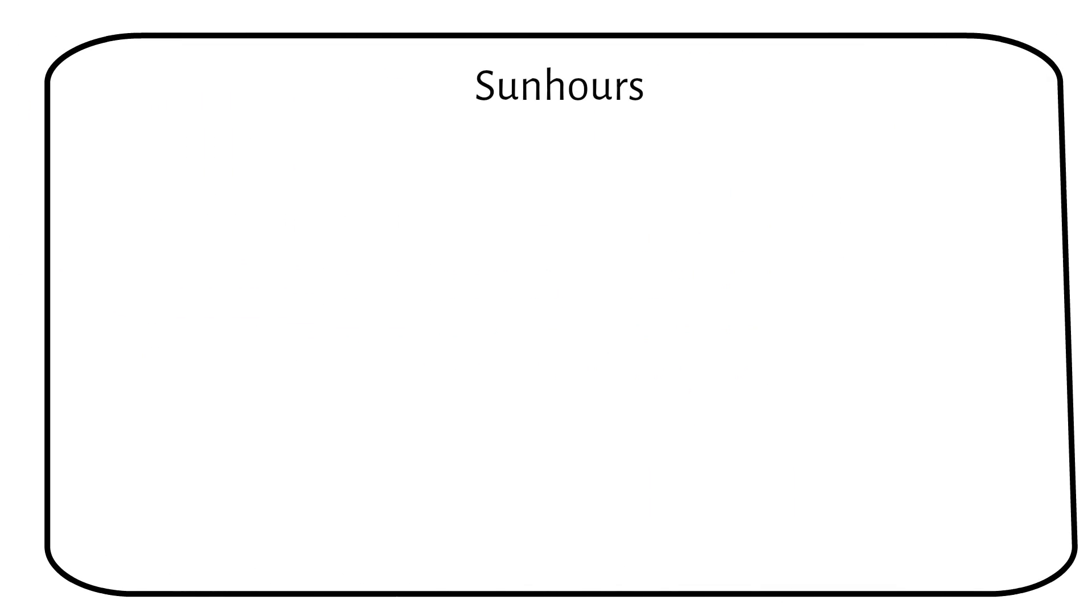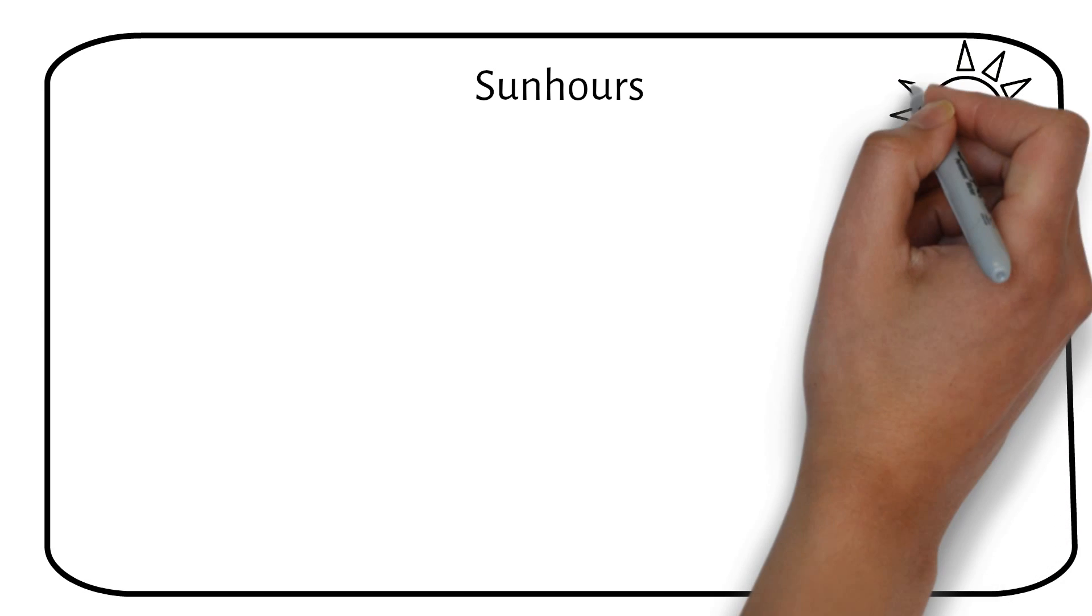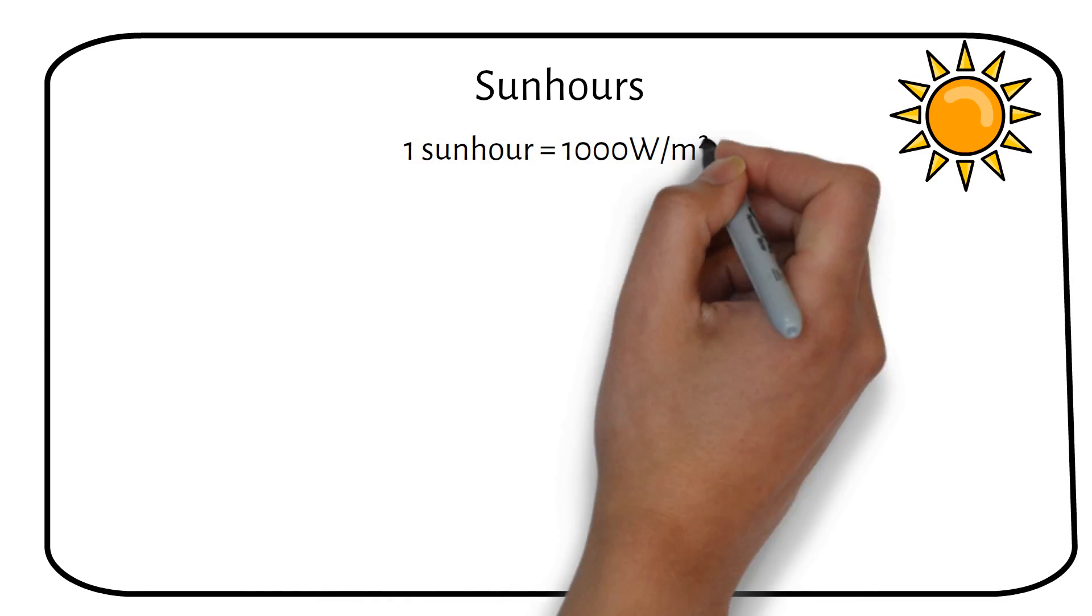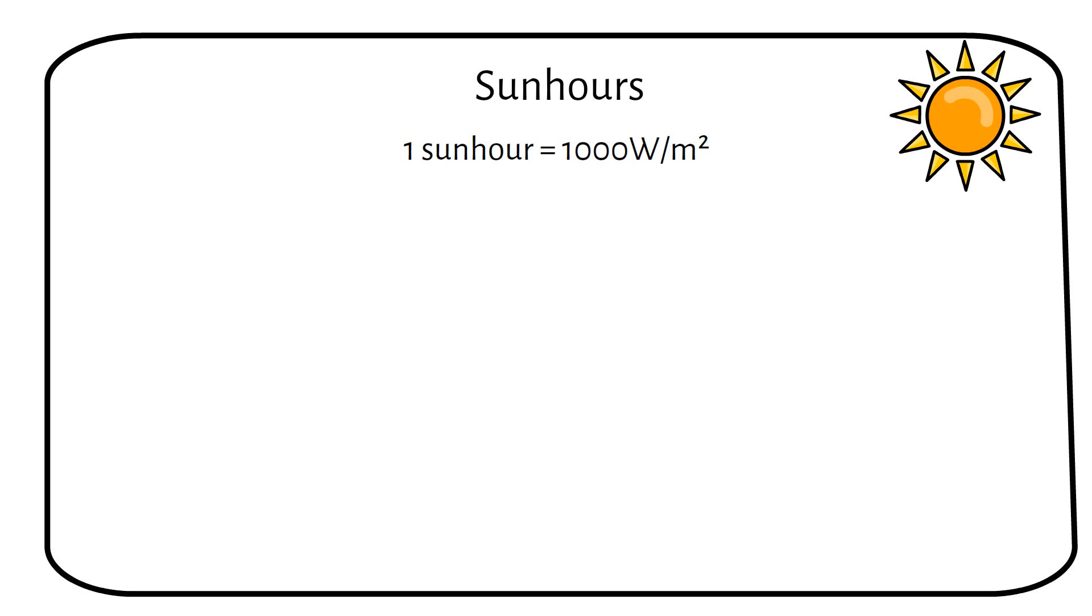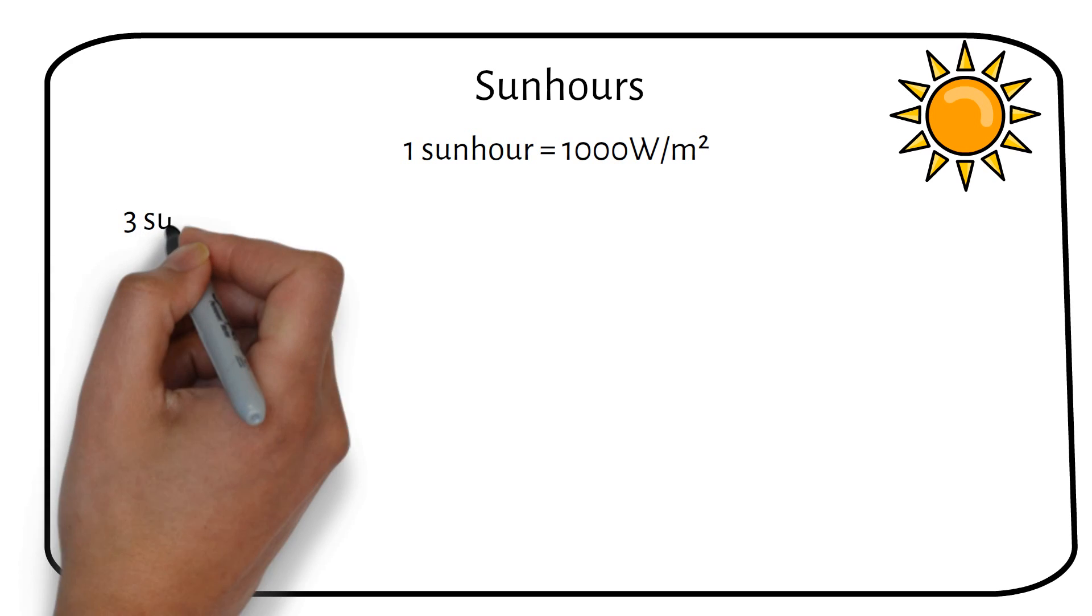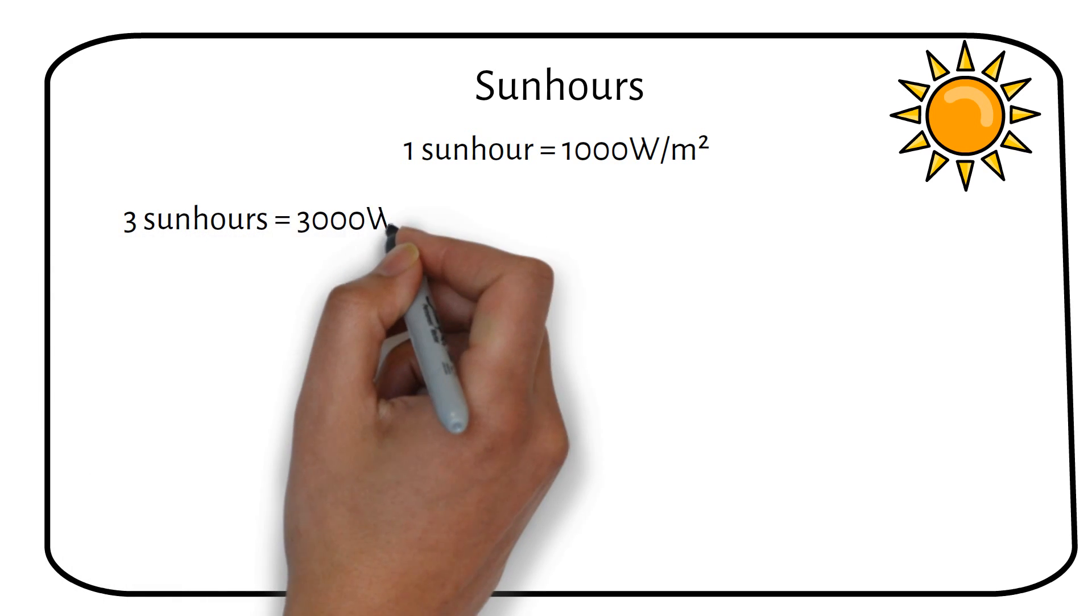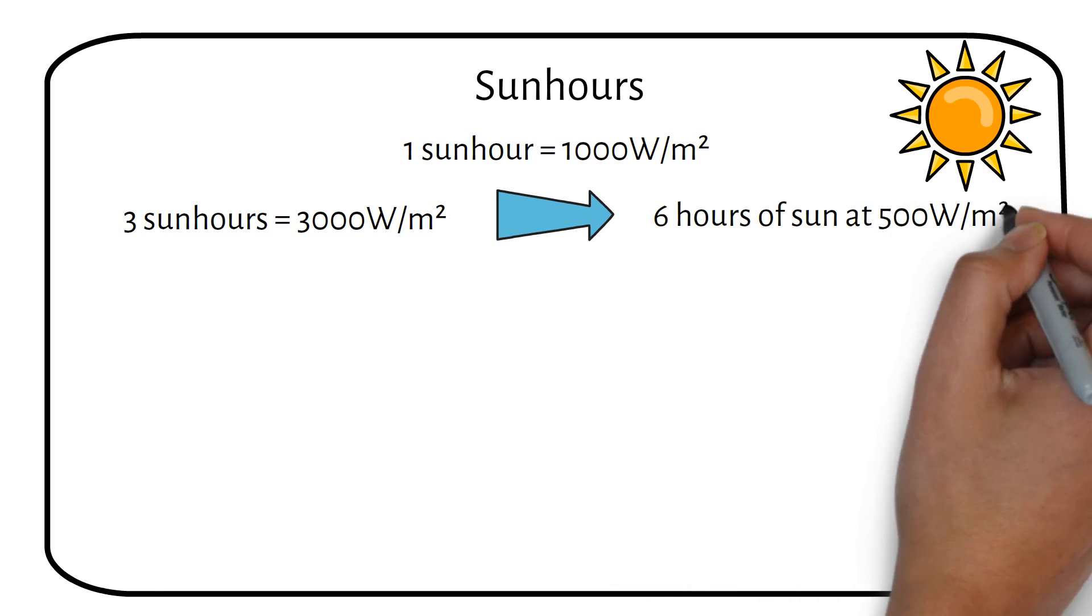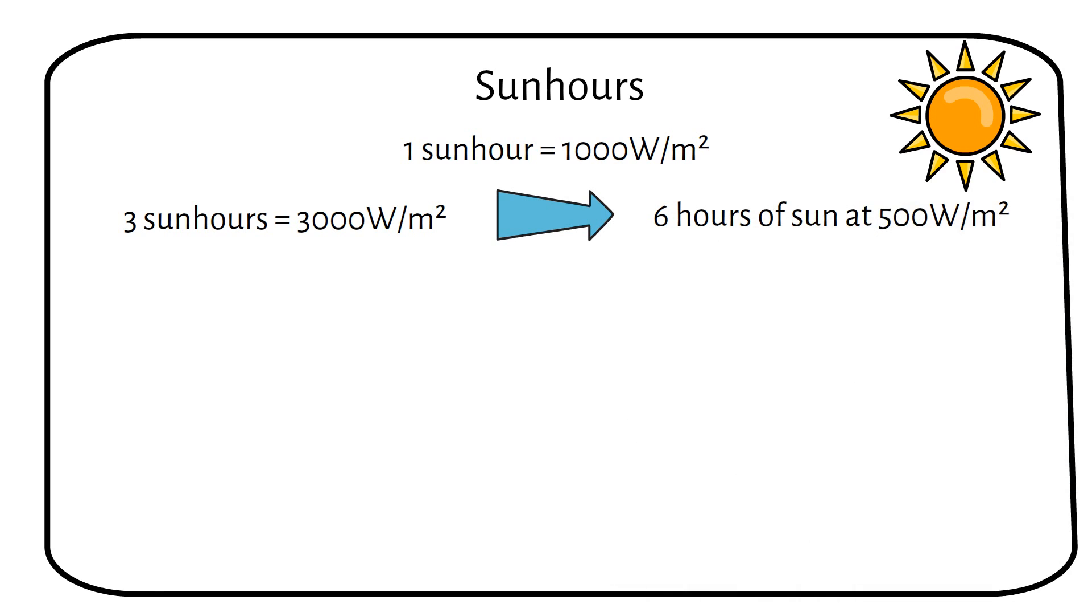Some people get confused about sun hours. Let me explain. One sun hour is 1,000 watts per square meter. You should not confuse this with the actual time the sun shines. Three sun hours is 3,000 watts per square meter per day, or 6 hours of sunshine at 500 watts per square meter. Sun hours varies by location and season.